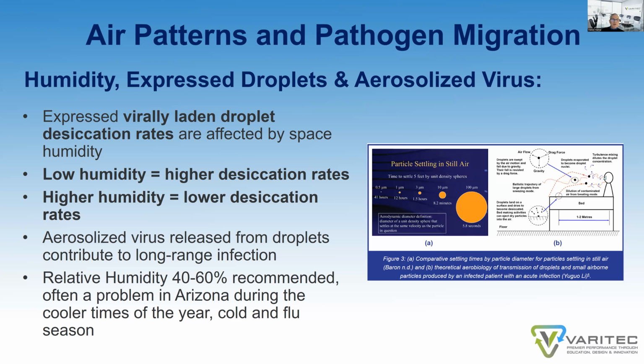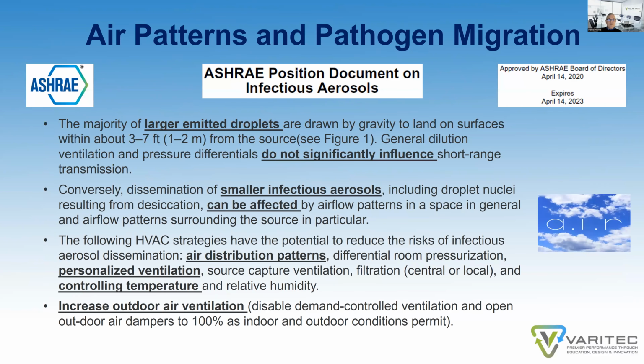So low humidity environments increase desiccation rates of virally laden droplets, allowing for aerosolized pathogens to be released into a space. Higher humidity environments equal lower desiccation rates, which is what you want, so the droplets maintain their mass and allow gravity to draw them from the space. ASHRAE recommends a relative humidity of about 40 to 60% RH. And of course, we know that flu and cold season here in Arizona is our driest time of year, as it is in any other part of the nation.